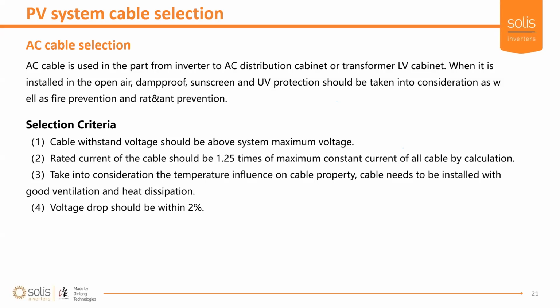The last one, the voltage drop, often gives us technical support guys a headache, because if the cables weren't designed properly, then the inverter reports that over grid voltage alarm, and everyone goes straight to the inverter being the issue, where in fact it is clearly a design fault.